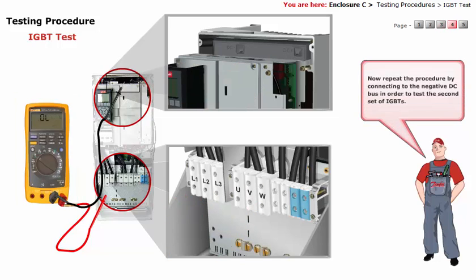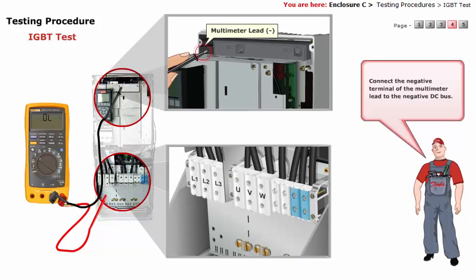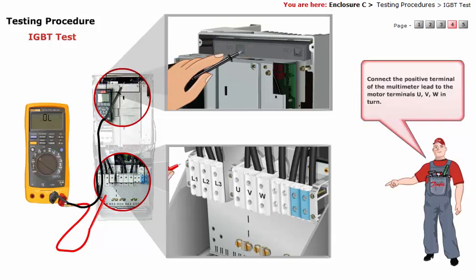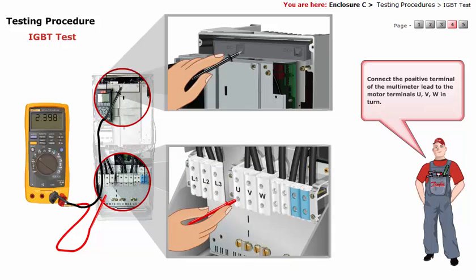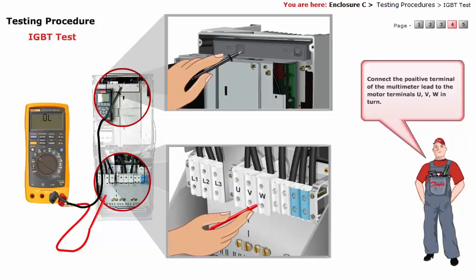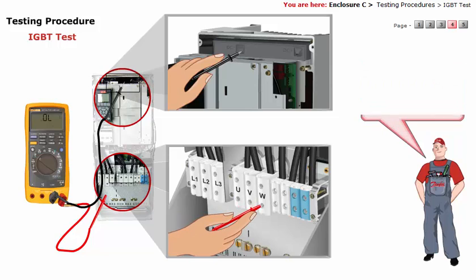Now, repeat the procedure by connecting to the negative DC bus in order to test the second set of IGBTs. Connect the negative terminal of the multimeter lead to the negative DC bus. Connect the positive terminal of the multimeter lead to the motor terminals U, V, W in turn. The multimeter should show the diode open.